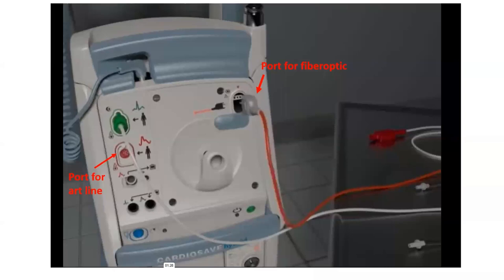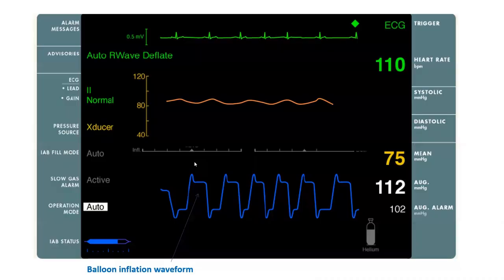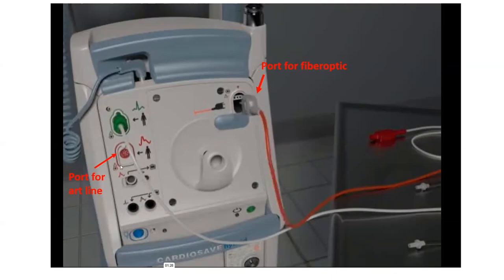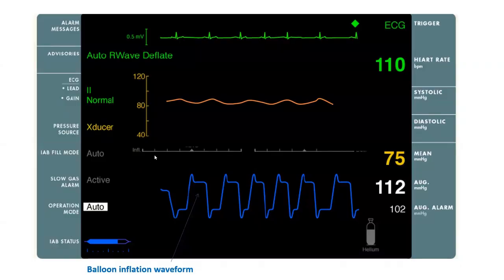There is another troubleshooting idea that I alluded to earlier. So you have a case like this one where the gas waveform is appropriate and properly timed to the EKG, but the arterial waveform is flat or distorted or totally erratic or totally absent. The issue in this case is dysfunction of your arterial monitoring line. Would it be your fiber optic line or your arterial lumen? It's not an issue with augmentation itself or with the balloon catheter. The patient is still getting proper augmentation. You and the balloon console are just not able to monitor it.